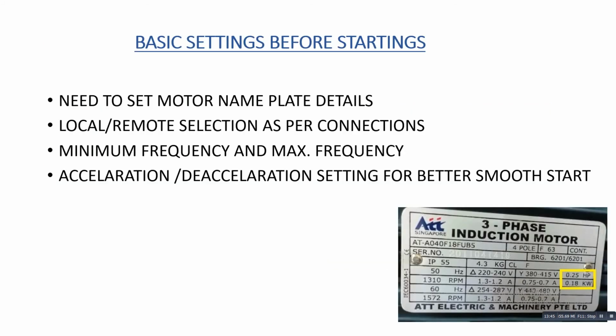Now we will see some basic settings before starting. Before you start, you have to make sure of some settings. The first one is you have to set the basic motor details, which are mentioned on the motor nameplate. You have to feed all the details like kilowatt or HP details, voltage, rated current, and rated kilowatt.